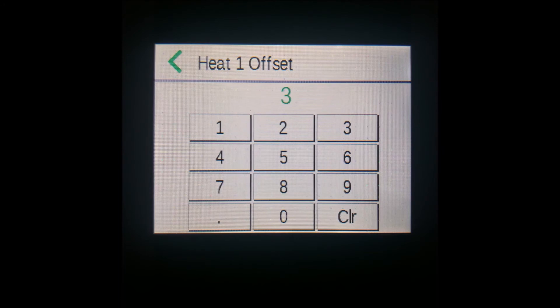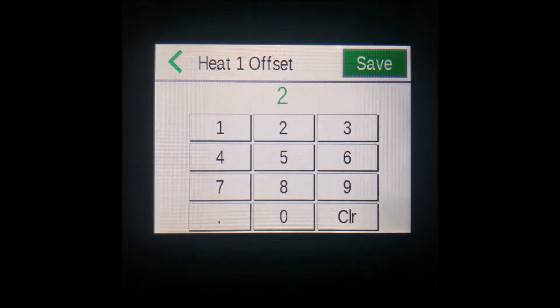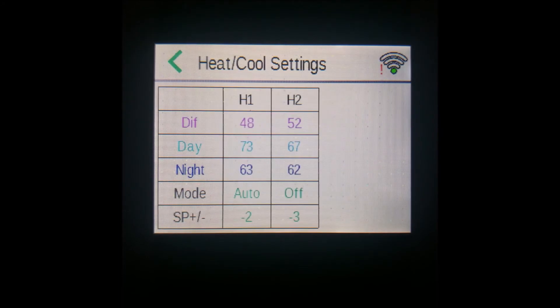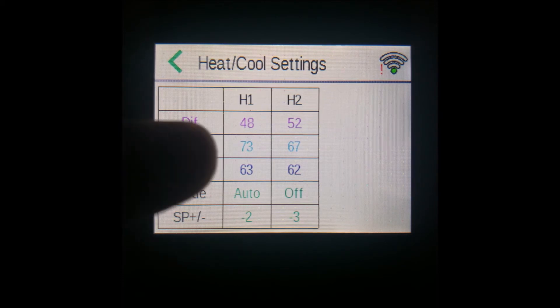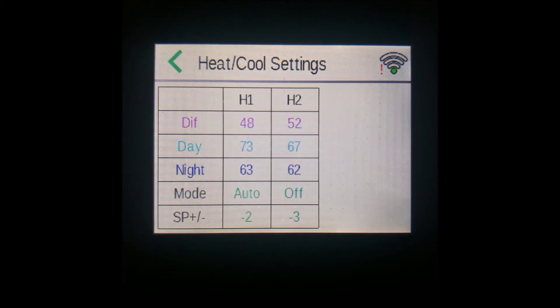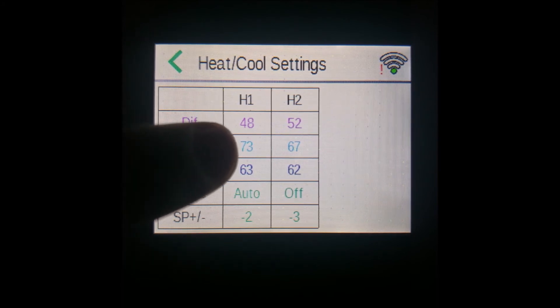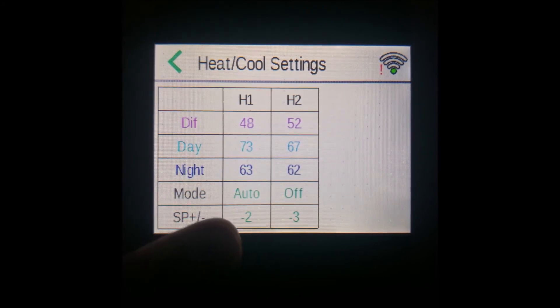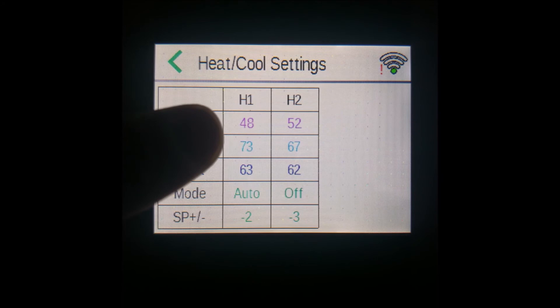For example, changing this heat one value from three down to two. Noting that this will automatically change to a negative value because this is a heat, you can now see the output temperatures change accordingly. For day, it was at 72, and now it's only taking two from 75, so it's at 73. Same goes for the diff and night.